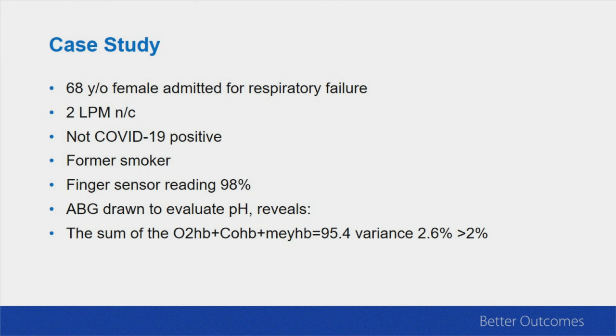So now that varies from the pulse ox reading of 98% by 2.6%. So that's greater than 2. And the way we are in medicine, if it's to be plus or minus 2, well, then the answer is it's to be plus or minus 2. So we have a variance here. So it's not within the normal range. But we would look at that number of 95.4 and we're going to say, well, we're still okay. Our patient's not hypoxic. But let's look at the breakdown.